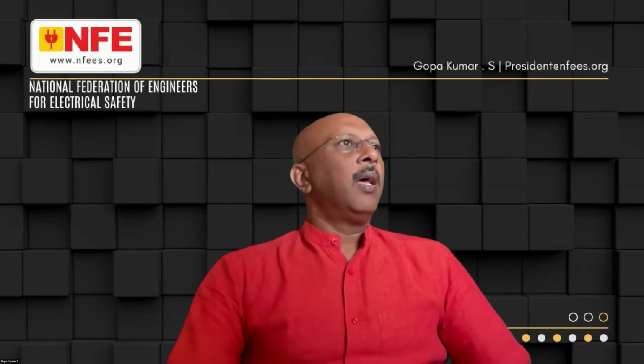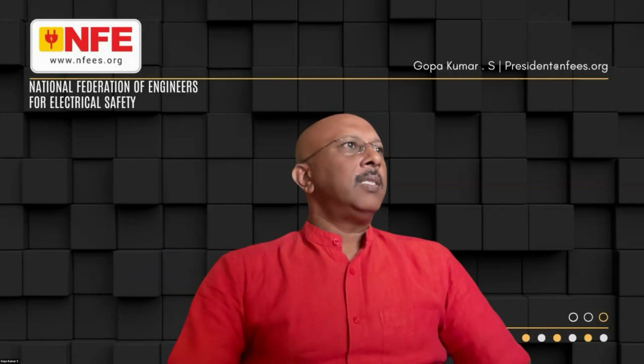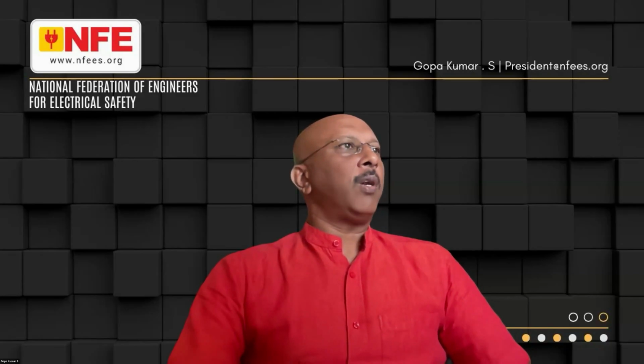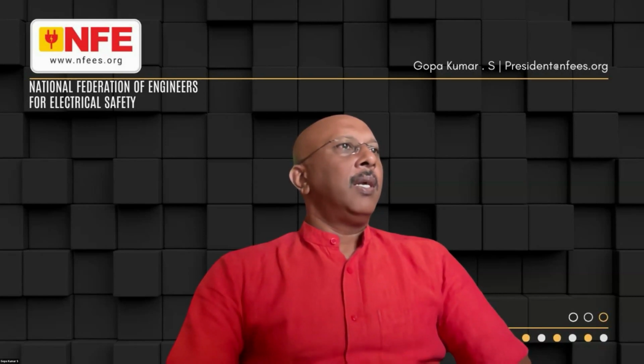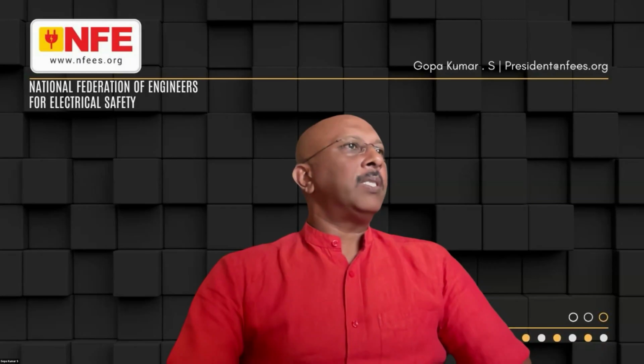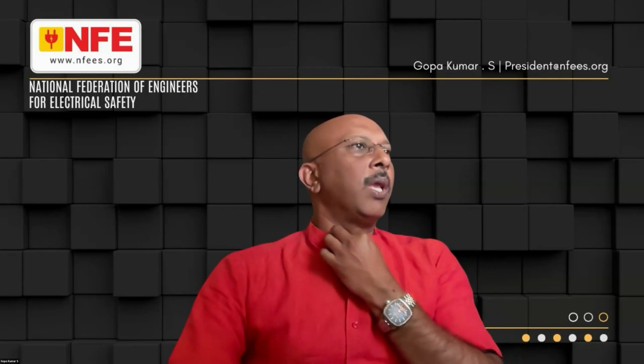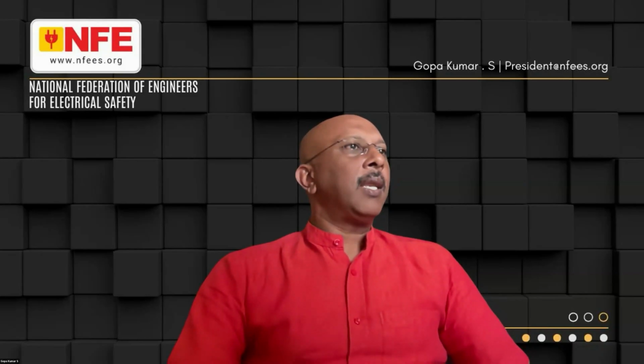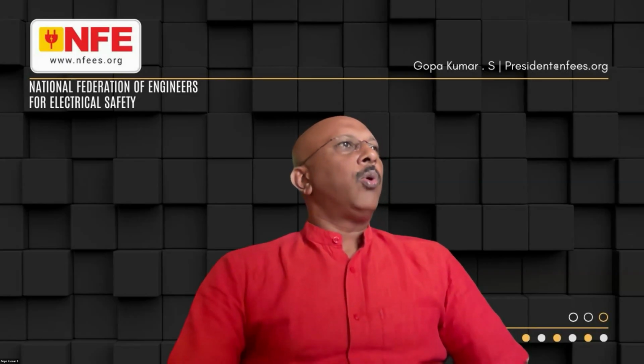Yeah, in an existing hospital with multiple earthings already set up: 2 for transformer neutral, 2 for TX body, meaning transformer body, 2 for DG, 2 for DG body, X-ray 5 numbers, CT scan 5 numbers, cath lab 6. So totally say 60 earth pits. TX and neutral grounding and a 3.5 core aluminum cable panel are provided. 4 pits are present which run along the electrical shaft. 2 core cable have been connected. Now when I am conducting an electrical audit, should I refrain from measuring individual earth pit resistance? Should I go ahead with only the fault loop impedance test? If yes, in such a complex earth system for a 9-story hospital, with no equipotential bonding, how can I conduct fault loop impedance? So, Mr.